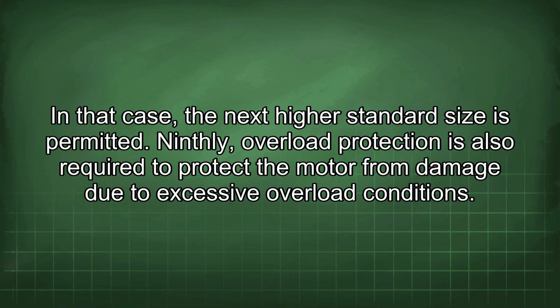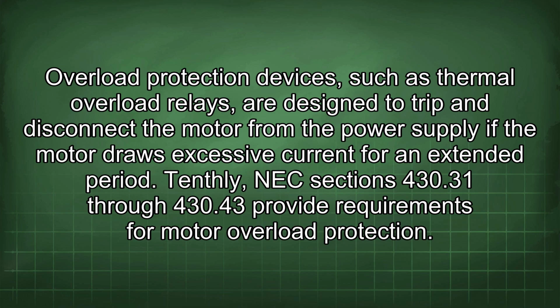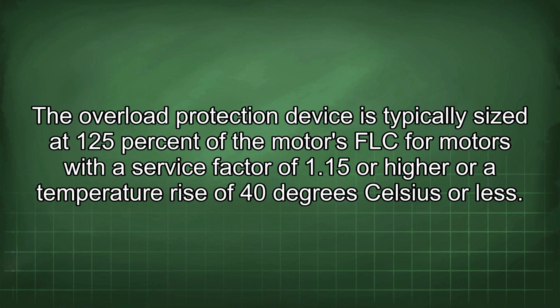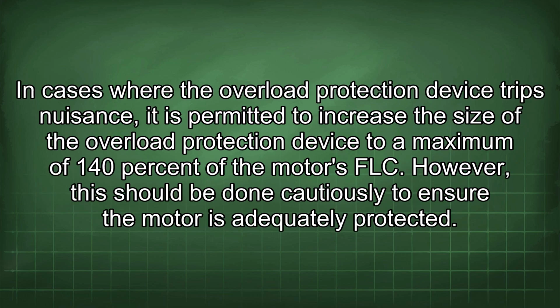Ninthly, overload protection is also required to protect the motor from damage due to excessive overload conditions. Overload protection devices, such as thermal overload relays, are designed to trip and disconnect the motor from the power supply if the motor draws excessive current for an extended period. Tenthly, NEC sections 430.31 through 430.43 provide requirements for motor overload protection. The overload protection device is typically sized at 125% of the motor's FLC for motors with a service factor of 1.15 or higher, or a temperature rise of 40 degrees Celsius or less. In cases where the overload protection device trips nuisance, it is permitted to increase the size of the overload protection device to a maximum of 140% of the motor's FLC. However, this should be done cautiously to ensure the motor is adequately protected.